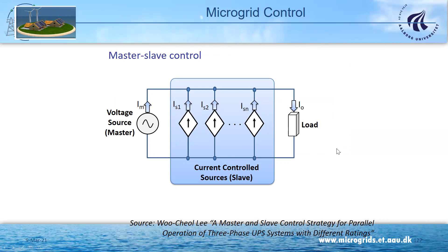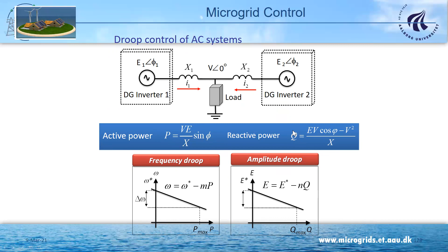What happens when we have a number of elements, for instance battery systems trying to be connected in parallel, is that small differences in phase, frequency, or voltage produce huge currents flowing from one converter to another. That's why we need to implement control loops inside to regulate it, using the transmission equations which tell us that small changes in frequency and power angle produce high differences in active power, while voltage affects more reactive power.